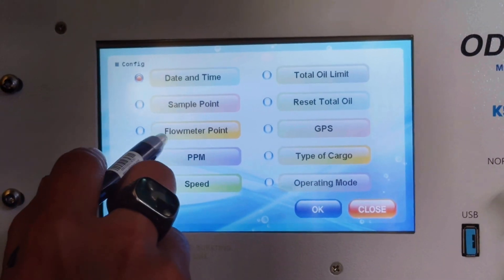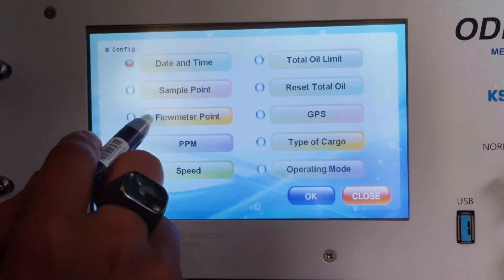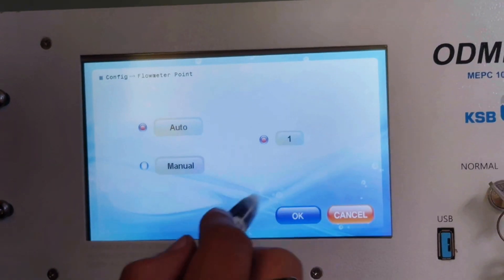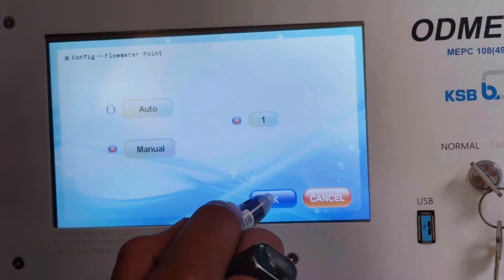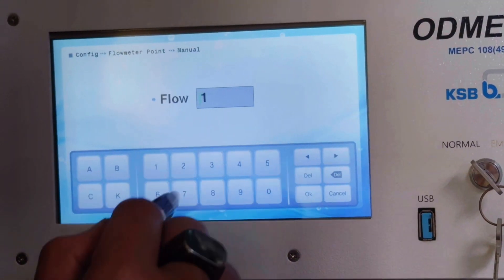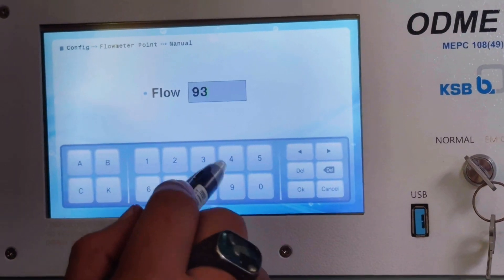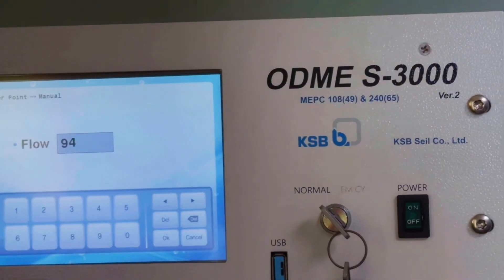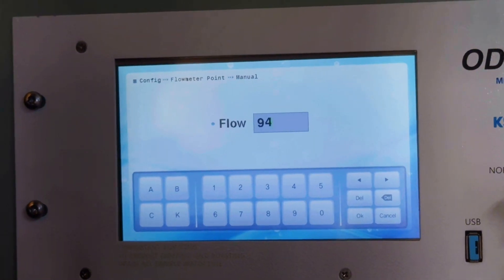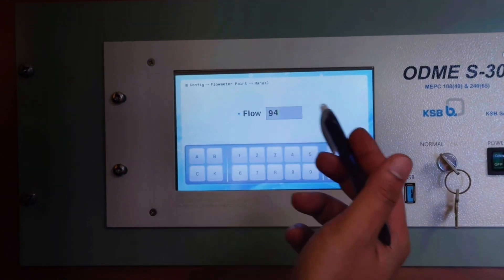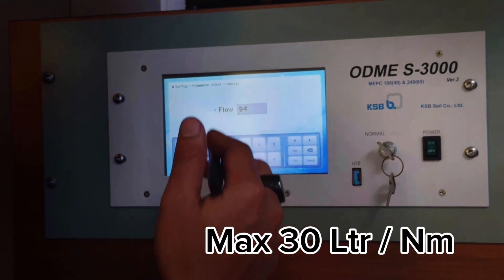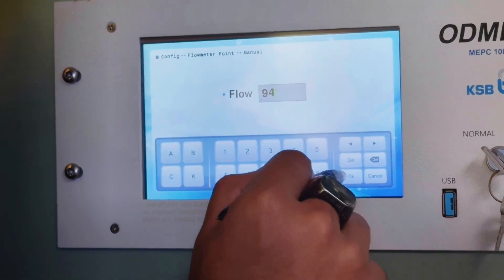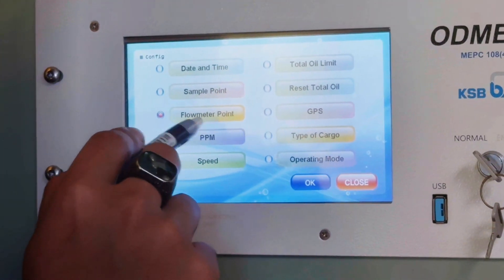Next we need to go to the flow meter. The sample point does not need to be changed. Go to flow meter, then select manual, and press OK to change the value. We will put the value 94. This value is guided by the ODME S-3000 manual as a predetermined setting, though you can choose any value within the limit of 30 liters per nautical mile. Press OK — flow meter setting is done.